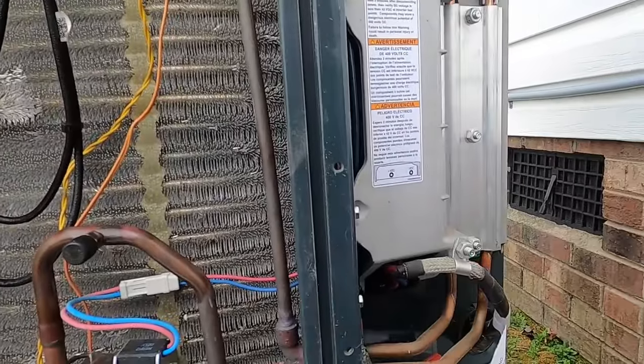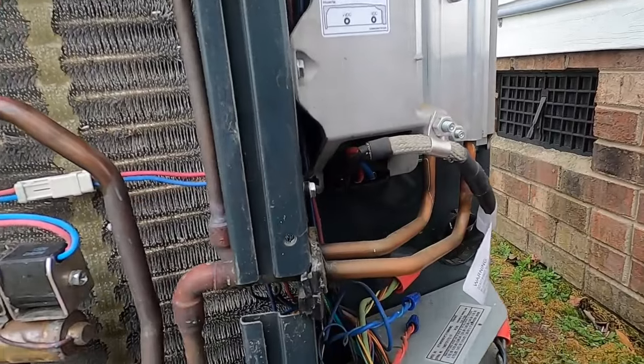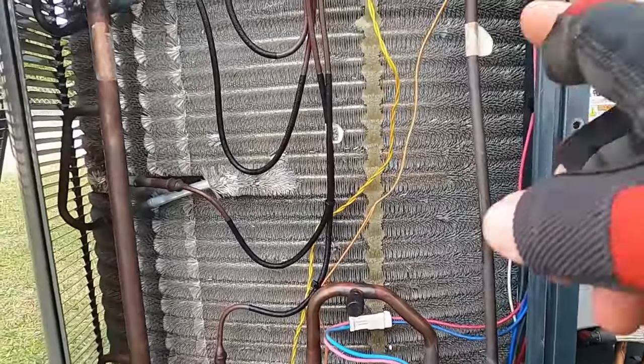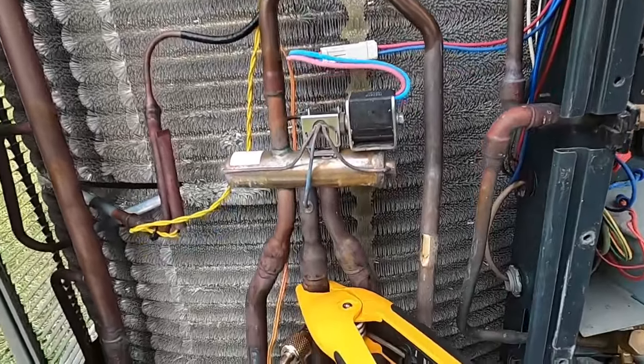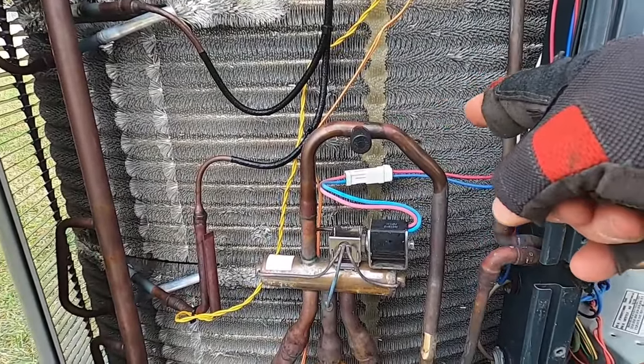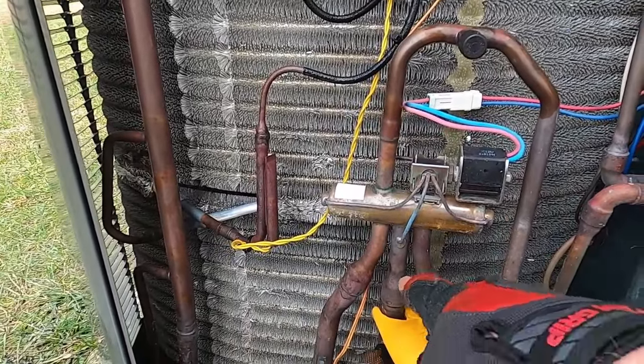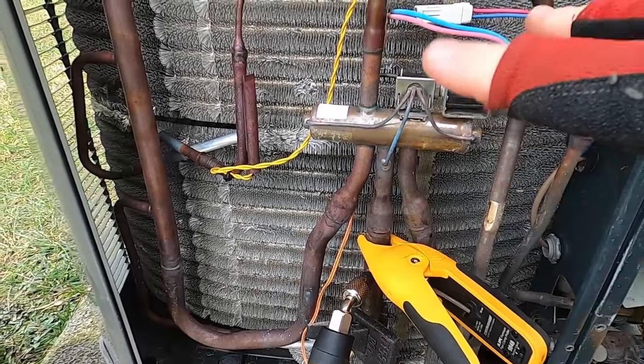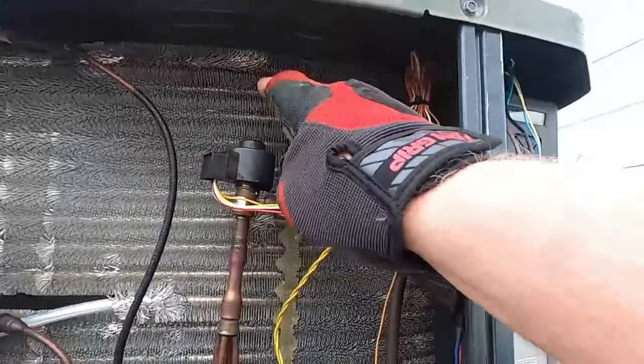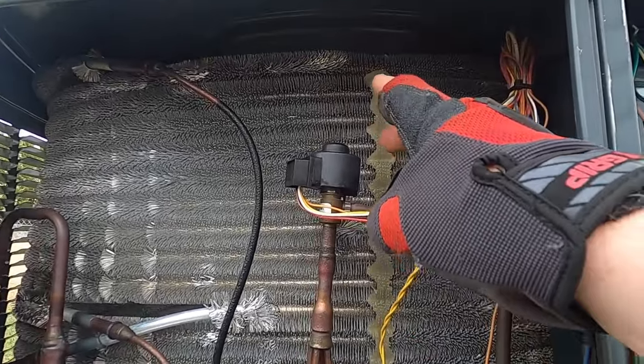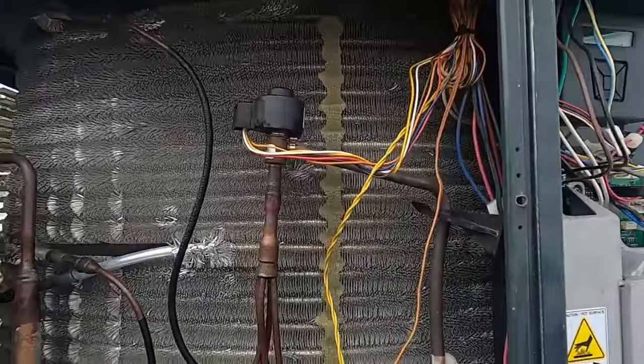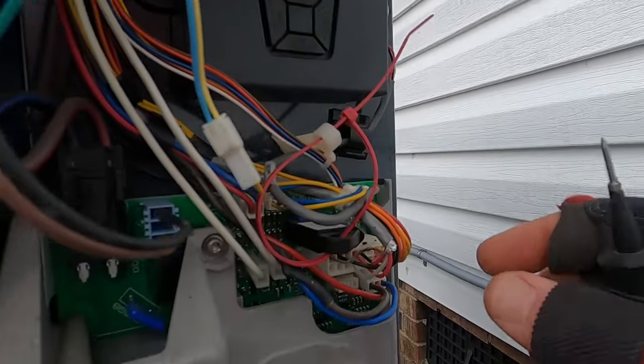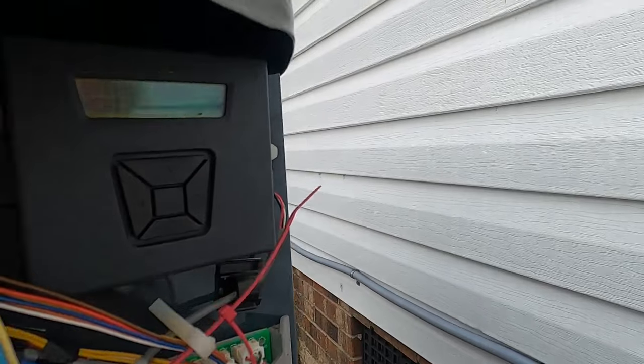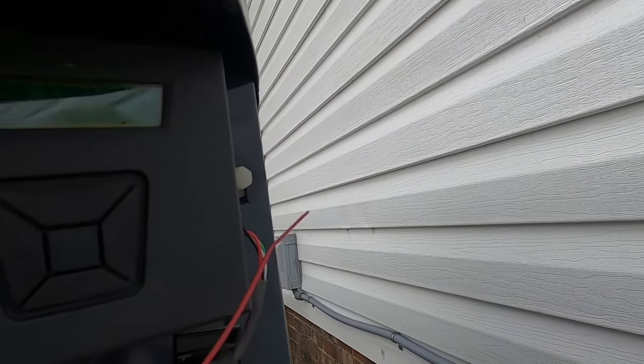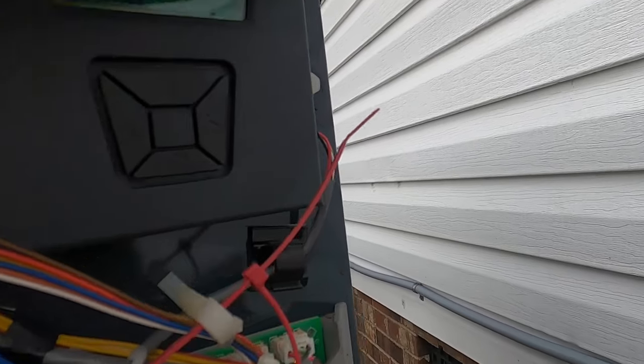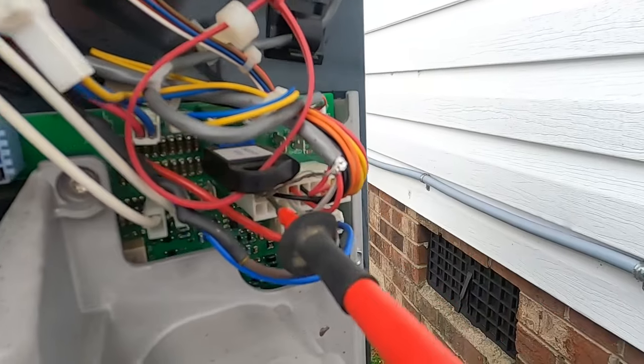And I probably explained it before, but we'll go over it again. You can check the transducer on this. The transducer is reading the true suction pressure inside the outdoor unit, correlating that to a temperature, the same way your gauges do. And this sensor is reading your true suction line, measuring the superheat across the system, and it's using that information to control this EEV with the stepper motor, to maintain the proper flow out here. That's how that works. Then my transducer is going to be this black wire. Get that wire out of the way.